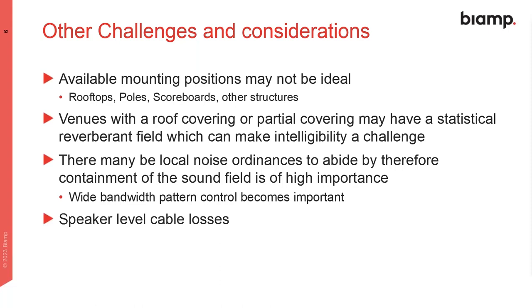Important subject. There's a lot of line loss calculators out there. In your handouts, there's actually a really good calculator and overview of how to use that calculator for constant voltage systems that will be very, very useful to you. But since cable runs for outdoor systems can often be much longer, we do want to take our cable gauging and sizing into account early on in the design process.